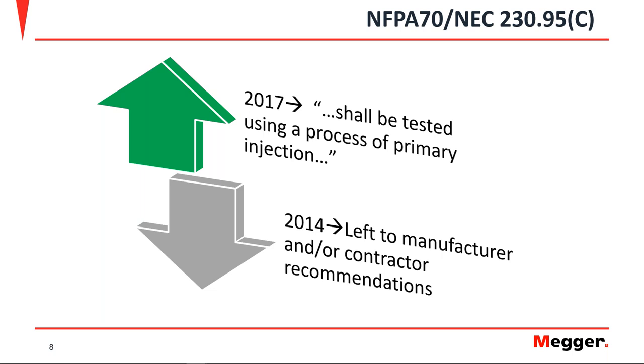That was changed in 2017. The latest version 2017 of the NEC changed clause C of that article, and now it requires us to test this Ground Fault Protection element with the primary injection method. This is a really big change — it's now a requirement to test, and it gives very clear instructions on which method to use: primary injection.